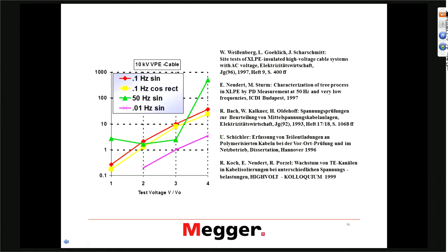The situation in Europe is a little different — there the standard only allows 0.1 Hz; it doesn't even allow 0.01 Hz. There is a difference, and the notion that it doesn't make a difference is incorrect, because something totally different happens in the cable installation at these two different frequencies.